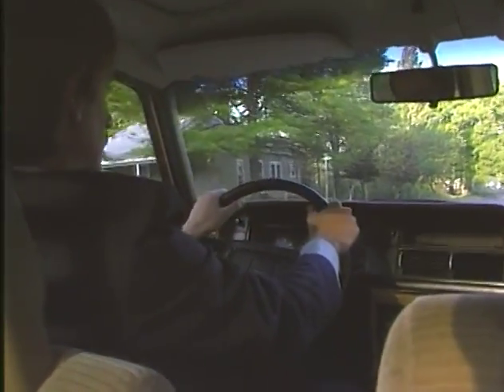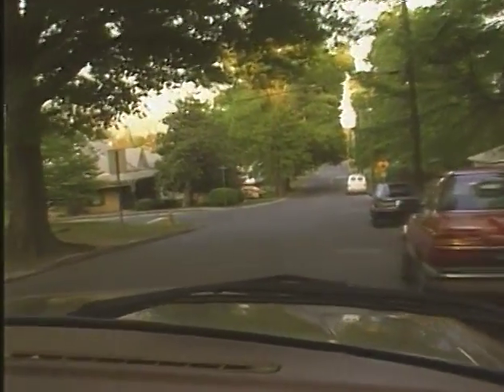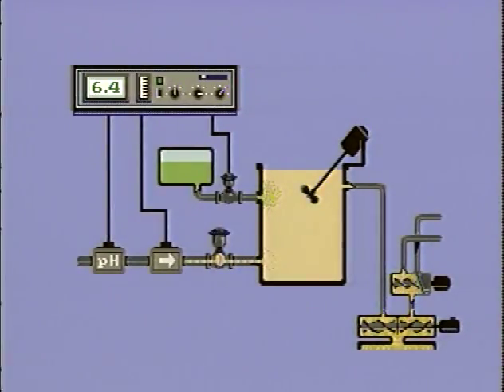Feed-forward control is more like the usual manner of steering. Objects can be dodged before a collision occurs, since they are spotted through the windshield. In the chemical plant, raw material was going to be accepted with a pH in the range of 6.2 to 6.8. The process required the pH to be between 6.2 and 6.4, so any variation in pH above 6.4 was a disturbance to the system that had to be corrected by adding an acid. With feed-forward control, it was possible to monitor the disturbance variables before they entered the reactor. A pH instrument was used to monitor pH, and a flow sensor was used to measure the flow. The feed-forward controller calculated the amount of acid needed to control pH at a desired value based on flow and/or pH disturbance. The output of the feed-forward controller positioned the valve to admit the required amount of acid to the stream to maintain the pH.